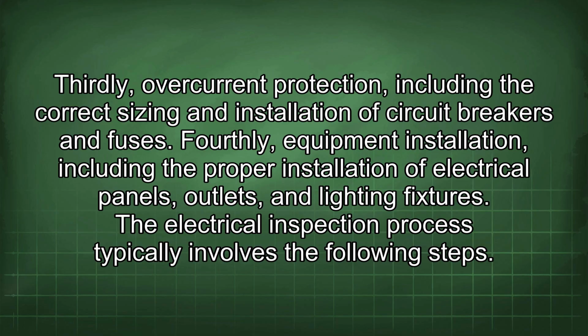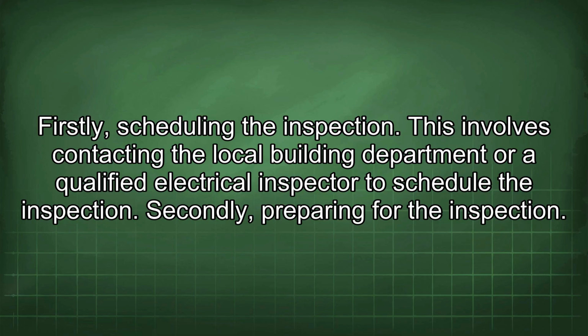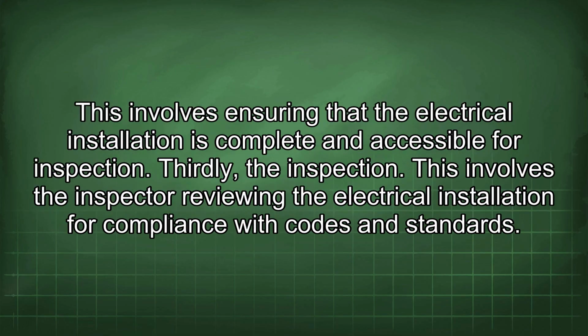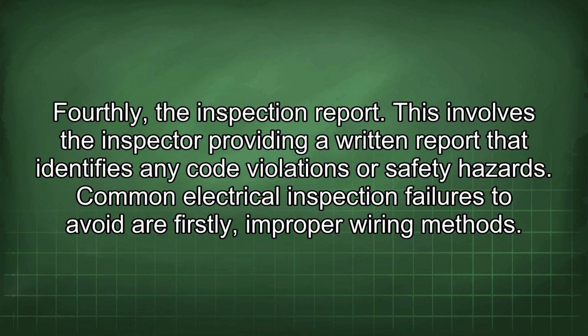The electrical inspection process typically involves the following steps. Firstly, scheduling the inspection. This involves contacting the local building department or a qualified electrical inspector to schedule the inspection. Secondly, preparing for the inspection. This involves ensuring that the electrical installation is complete and accessible for inspection. Thirdly, the inspection. This involves the inspector reviewing the electrical installation for compliance with codes and standards. Fourthly, the inspection report. This involves the inspector providing a written report that identifies any code violations or safety hazards.